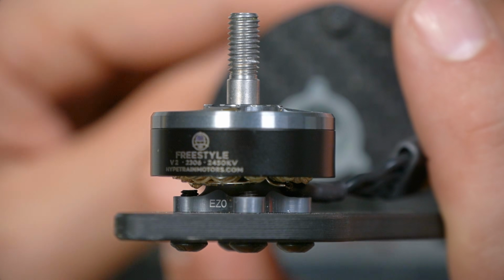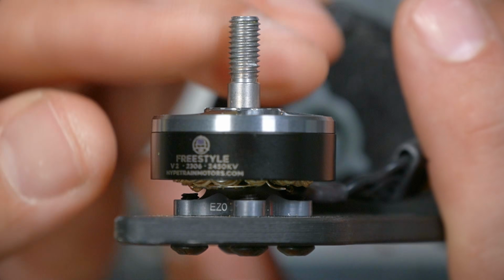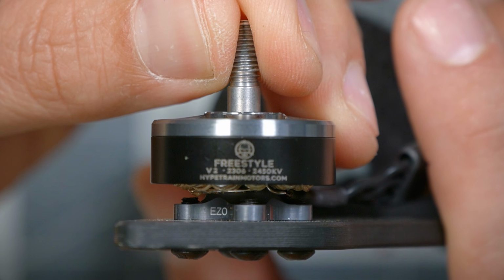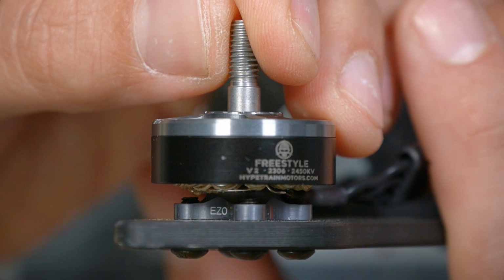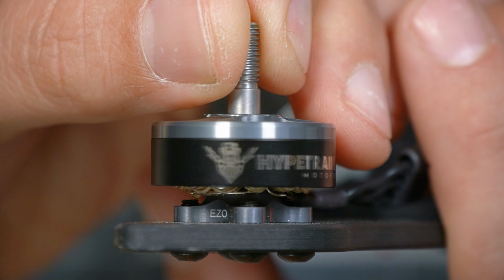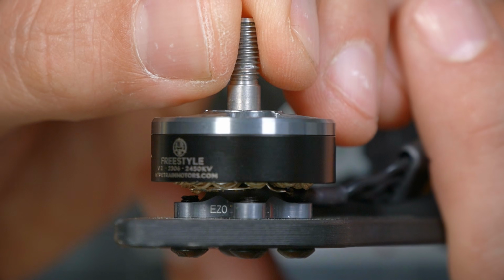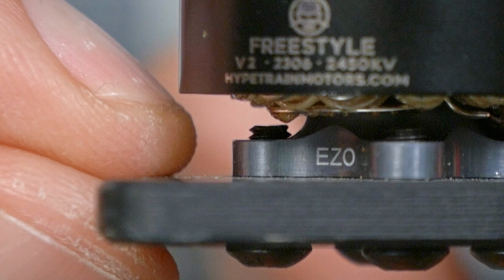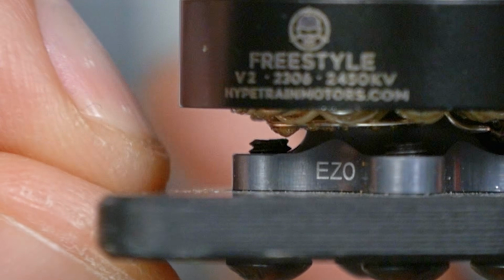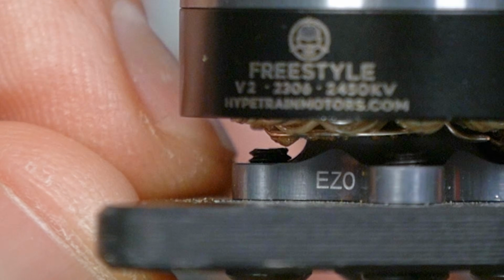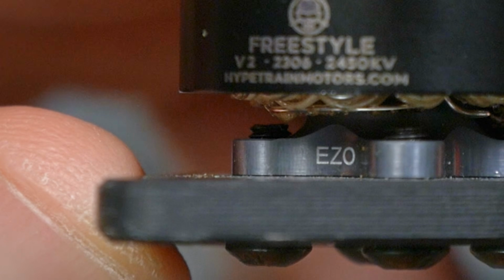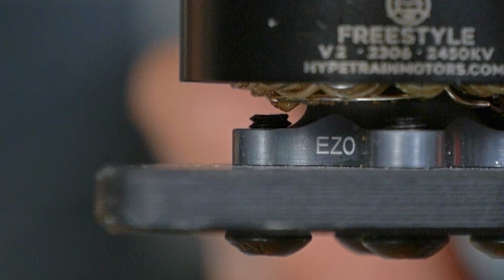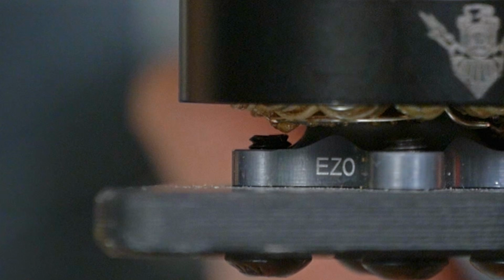So we're going to start our troubleshoot with a physical inspection of this motor, and we're just going to look and see if we can find any defects. The first thing I'm going to do is look at the motor edge on, rotate the motor bell, and look at this gap right here between the motor bell, the bottom of the bell, and the arm, or maybe the gap between the base and the bell. I'm going to eyeball a gap like that, rotate it, and see if that gap changes size. You could even use a caliper or a feeler of some kind to measure it. But what I'm looking for here is whether the shaft is bent and the bell is off center.